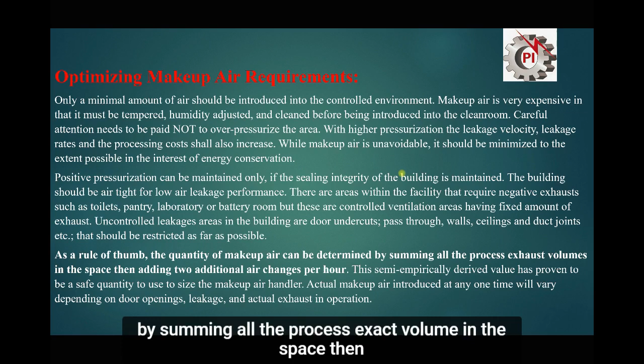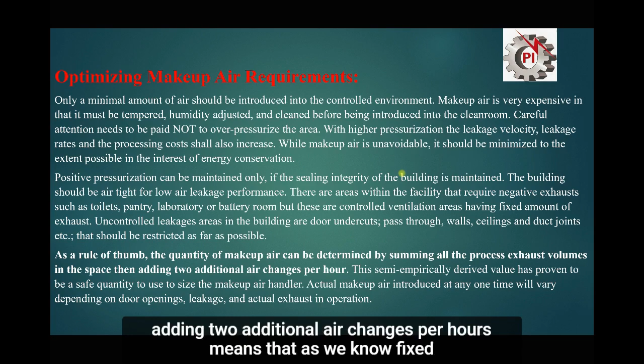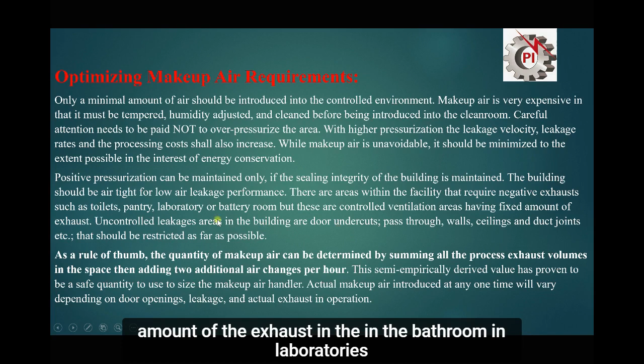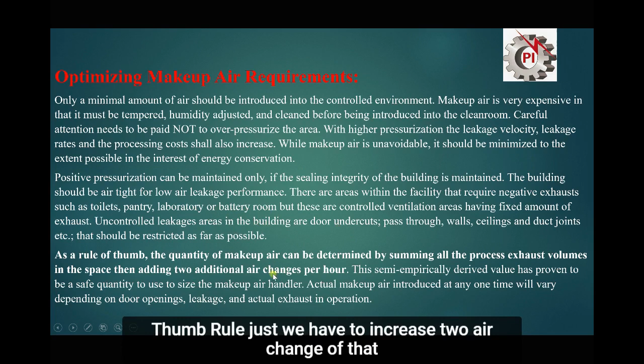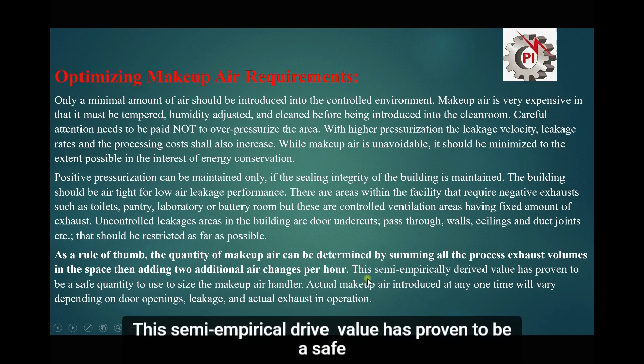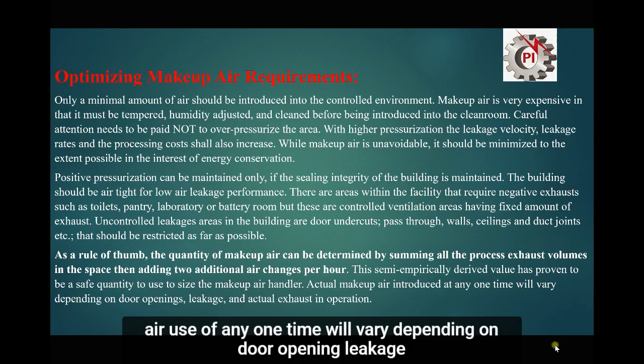As a rule of thumb, the quantity of makeup air can be determined by summing all the process exhaust volume in the space, then adding 2 additional air changes per hour. It means that, as we know, there is a fixed amount of exhaust in the bathroom and laboratory. If we know the amount of this fixed exhaust, then by the thumb rule we just have to increase by 2 air changes of that room so we can get the positive pressure. This semi-empirically derived value has proven to be a safe quantity to use to size the makeup air handler. Actual makeup air introduced at any one time will vary depending on door opening, leakage and actual exhaust in operation.